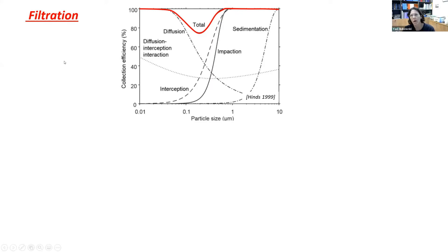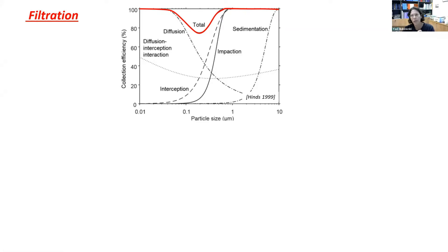Filtration is the most common and simplest technology for treating air pollution, focusing mainly on the particulate phase. As you can see in this figure presenting collection efficiency as a function of particle size, filtration involves several processes — diffusion, impaction, and interception. As a result of combining these processes, the most challenging size category to collect by filtration is around 0.2–0.3 microns, lying between the high efficiency of diffusion and the higher efficiency of impaction and interception.